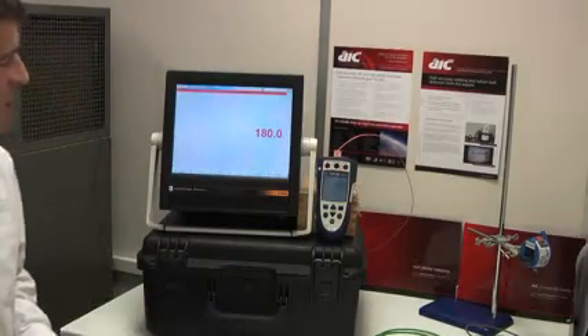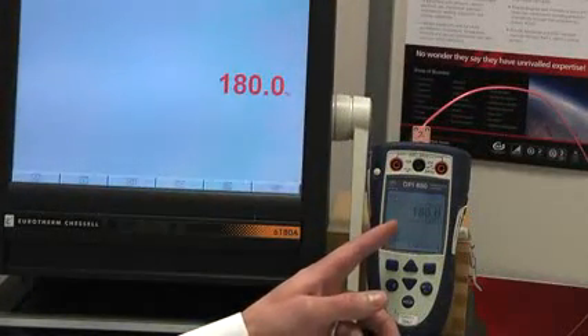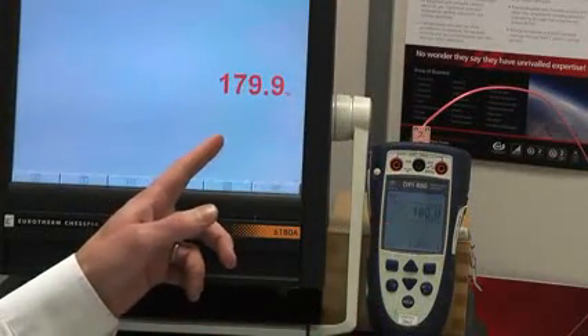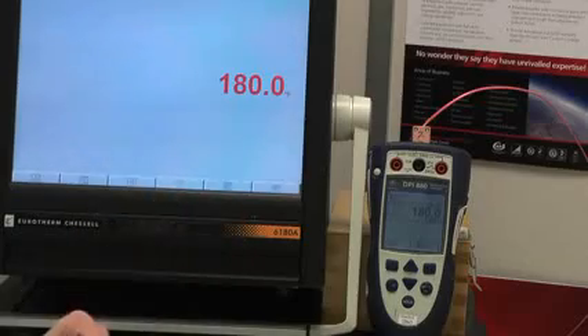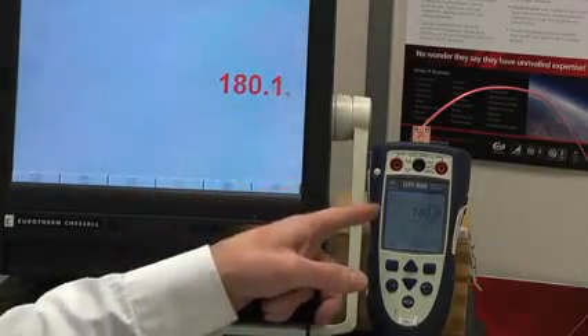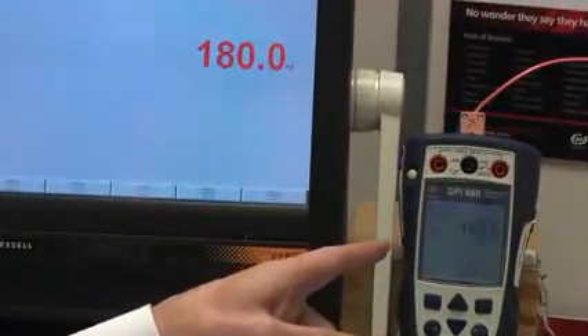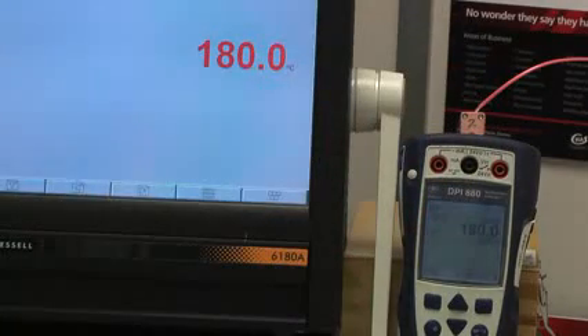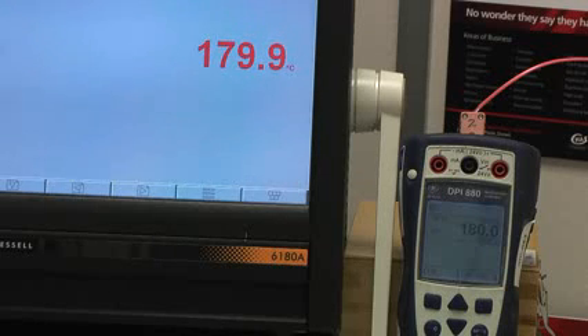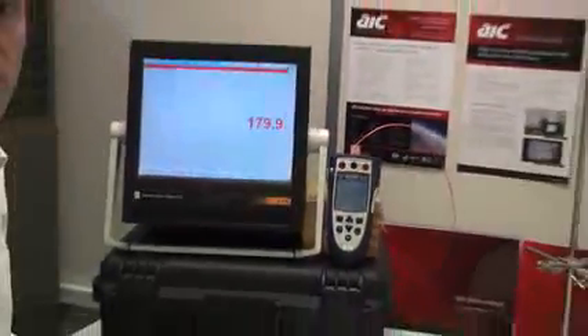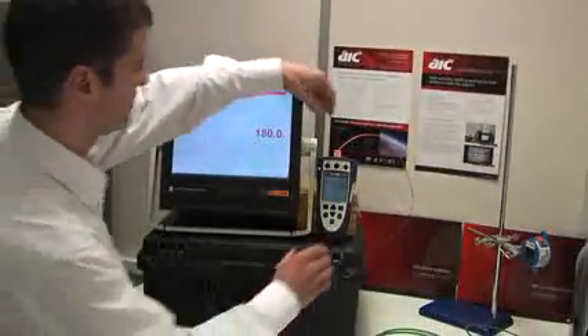So we can see here we have just a normal process calibrator and our field test instrument chart recorder, and they're both set up to read Type N calibration, and they're connected together with Type N thermocouple cable, and as you'd expect we've got a pretty accurate reading in there. So what I'm going to do is change the Type N cable for Type K cable, which is clearly not correct.